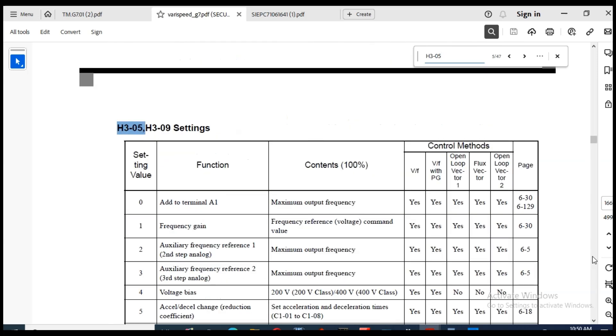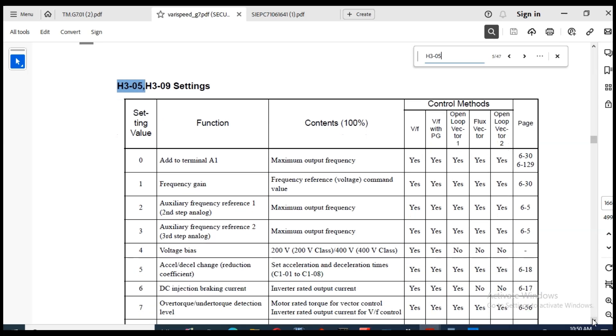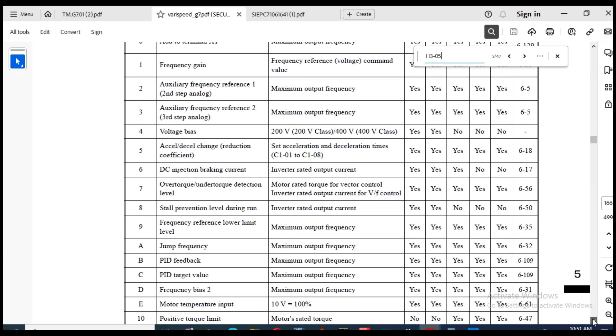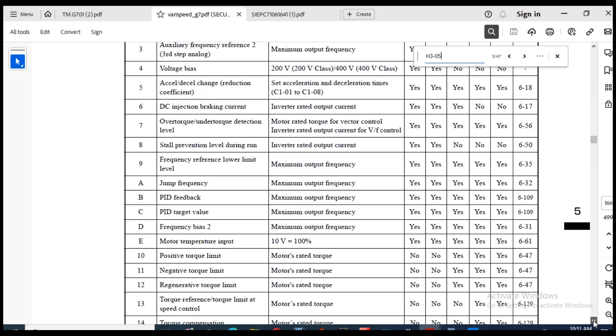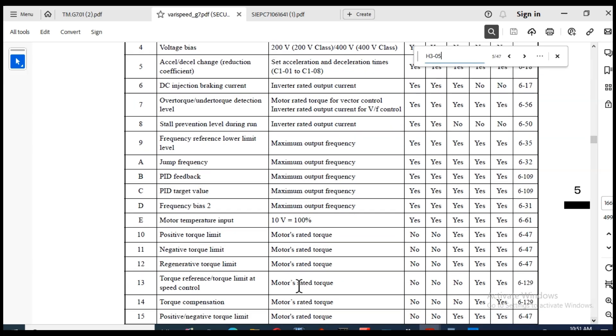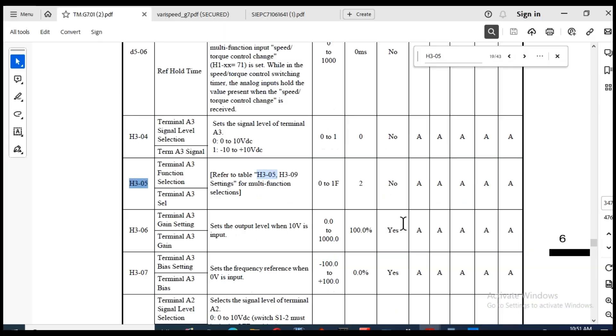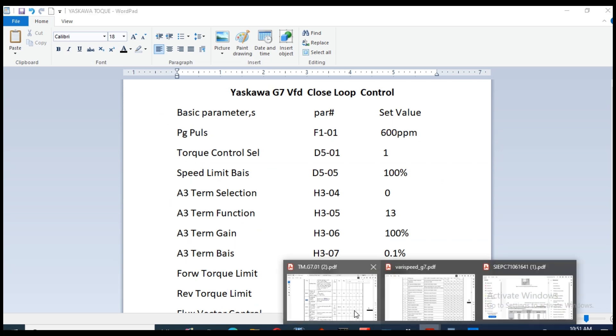Function selection. H3-05 set to 13 is torque reference and torque control, torque limit and speed control. H3-06 terminal A3 gain is set to 100%.